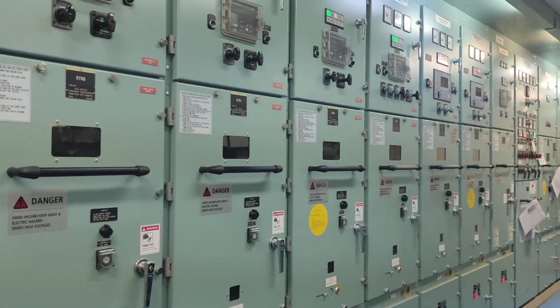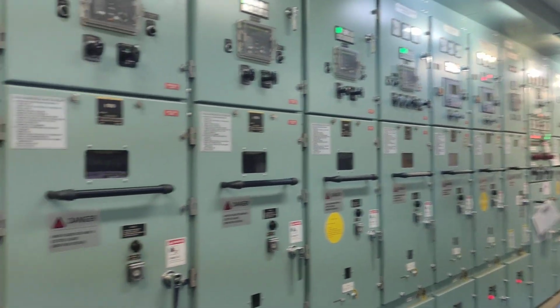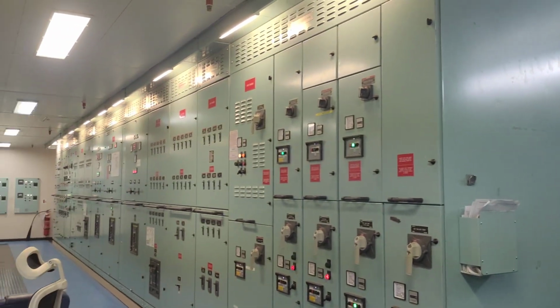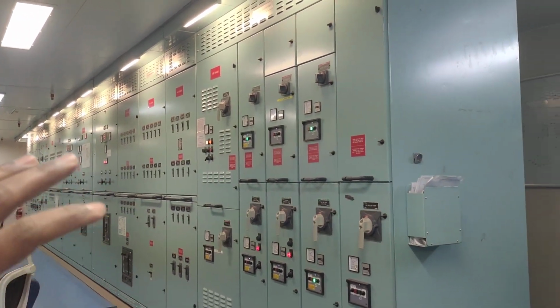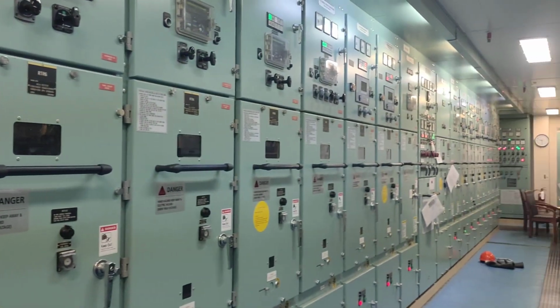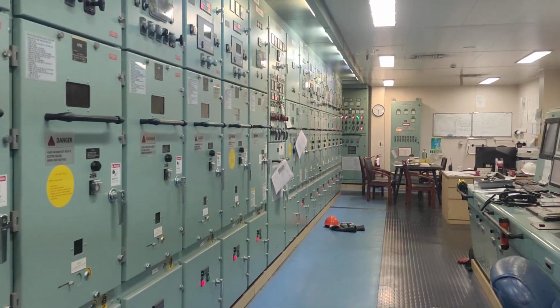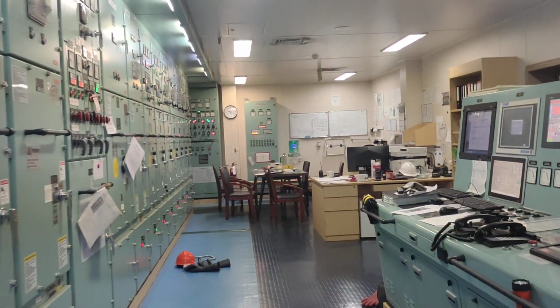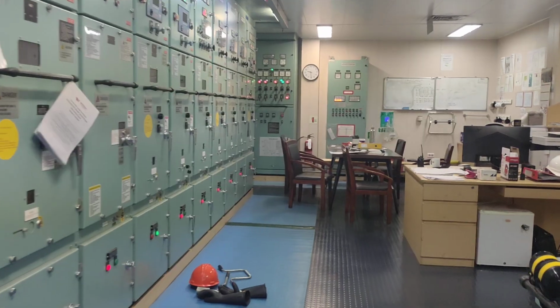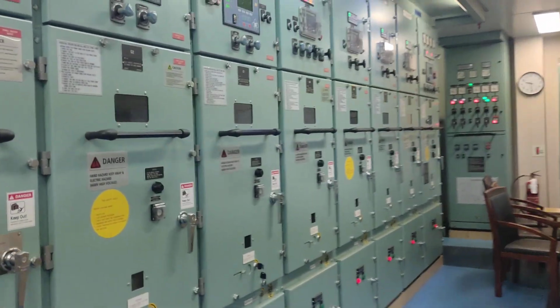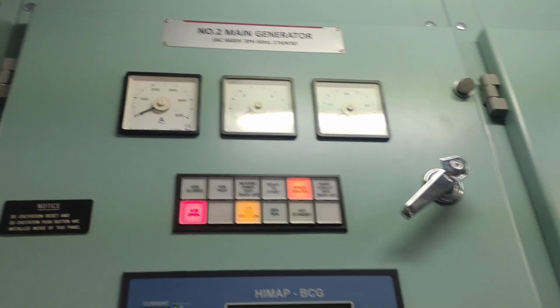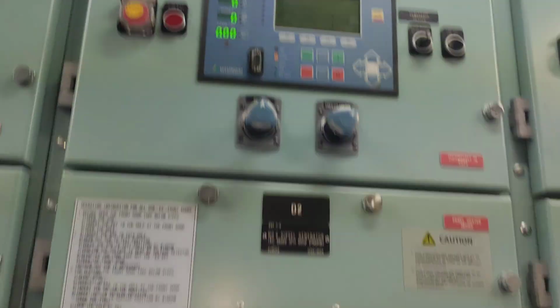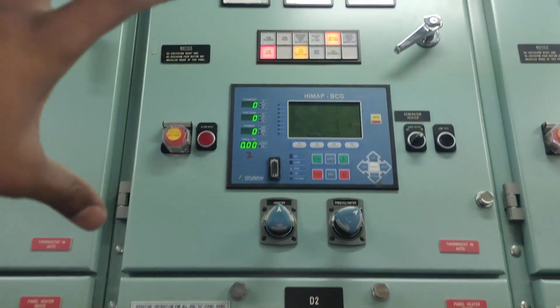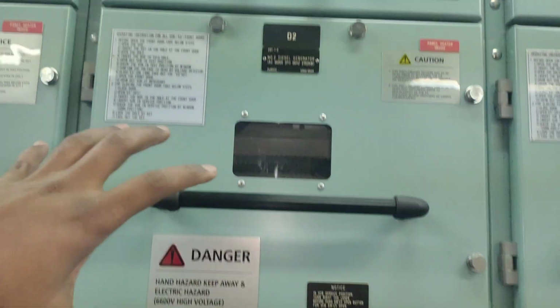This is our high voltage panel and this is our low voltage panel. Low voltage is 440 volt and high voltage, on our ship, is 6.6 kV. We are going to disconnect the VCB from number 2 generator. This is the VCB section, this is the control panel section for low voltage, this is the VCB section, and this is the earthing section.